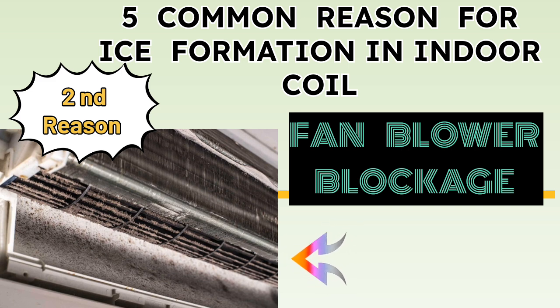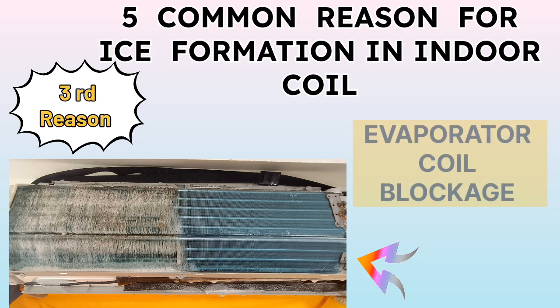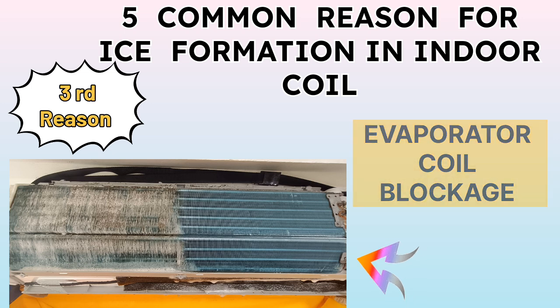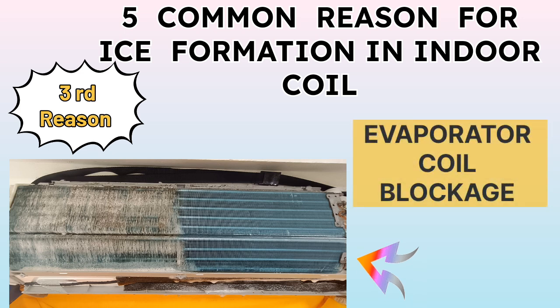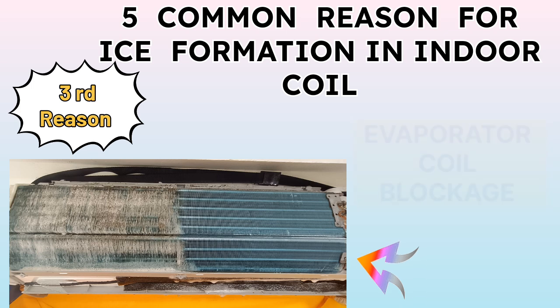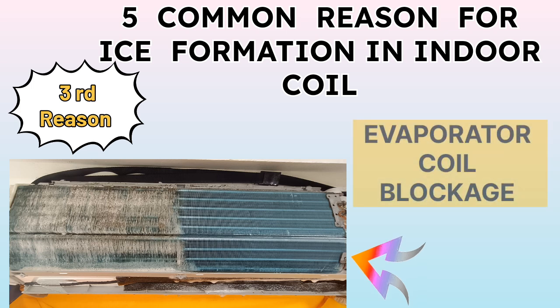The third reason is evaporator coil blockage. When we don't service our air conditioning, unwanted particles slowly settle on the indoor unit and it gets blocked. Due to that, the airflow is less and you can get ice formation in your indoor unit, and it will not cool as before. So always do servicing frequently and you will get proper cooling with no ice formation in your evaporator coil.